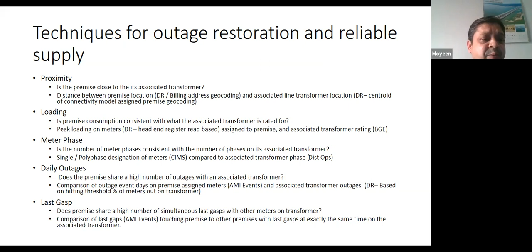Similarly for loading - consumers under the same transformer, some 2 kilowatt users show one load pattern, while other 2 kilowatt consumers show a different pattern. That could mean a leakage problem, an earth problem, tampering, or something else. So you can correlate this with the alarms in the meter as well.